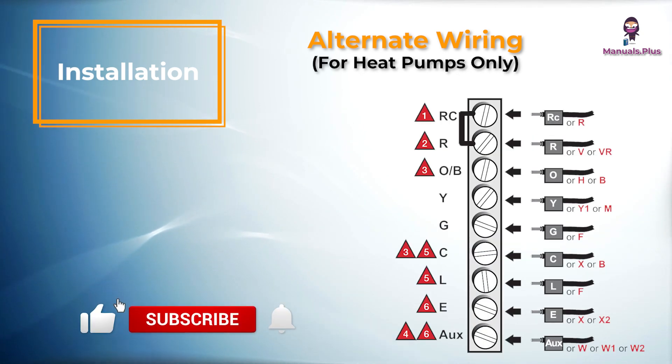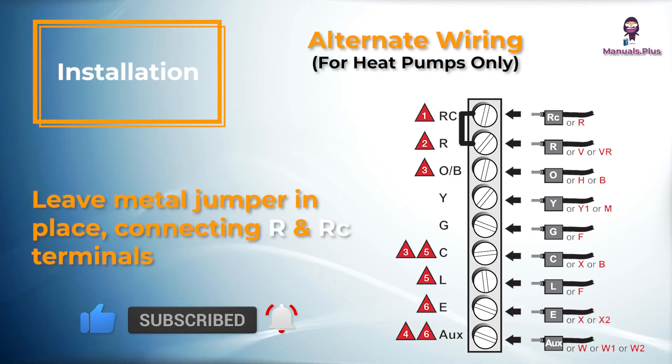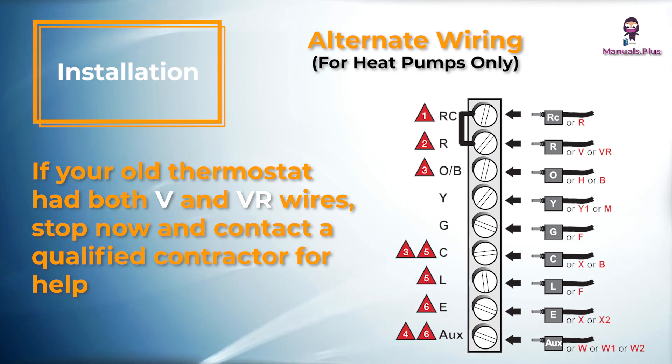Alternate wiring for heat pumps only: Leave the metal jumper in place connecting R and RC terminals. If your old thermostat had both V and VR wires, stop now and contact a qualified contractor for help.